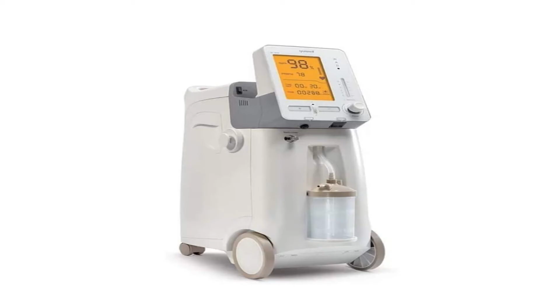How does it work? An oxygen concentrator is a medical device that concentrates oxygen from ambient air. Atmospheric air has about 78% nitrogen and 21% oxygen, with other gases making up the remaining 1%. The oxygen concentrator takes in the air, filters it through a sieve, releases the nitrogen back into the air, and works on the remaining oxygen. This oxygen, compressed and dispensed through a cannula, is 90 to 95% pure.